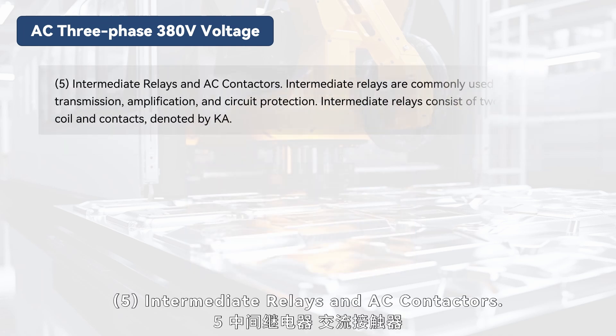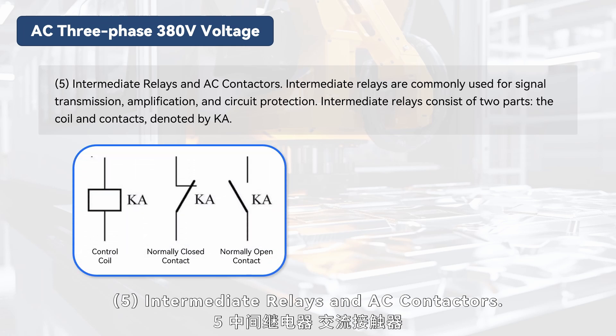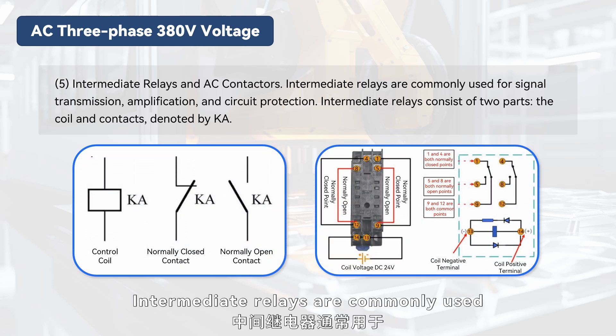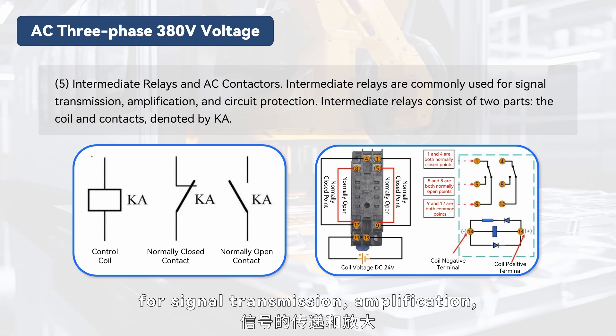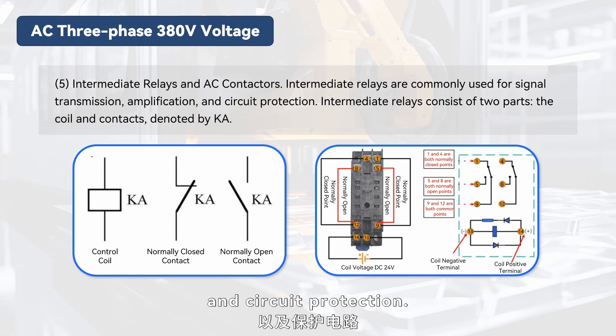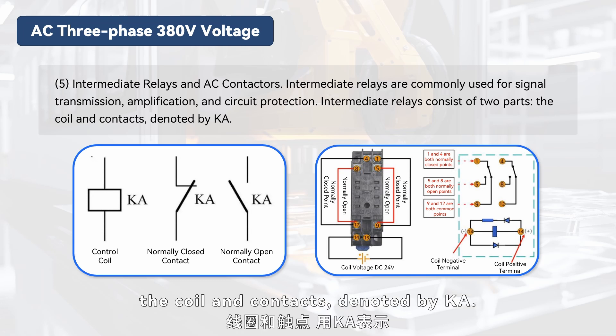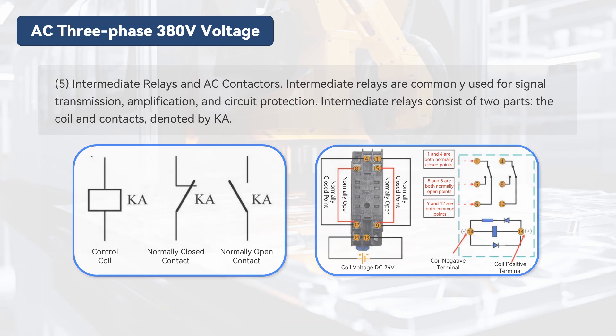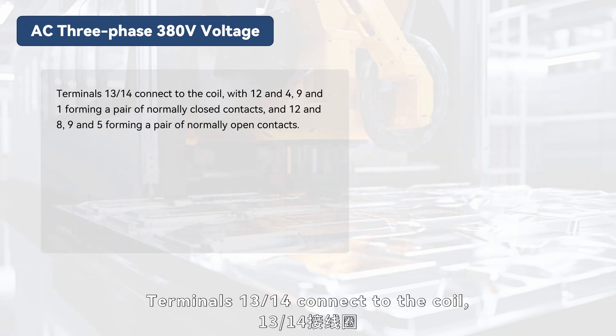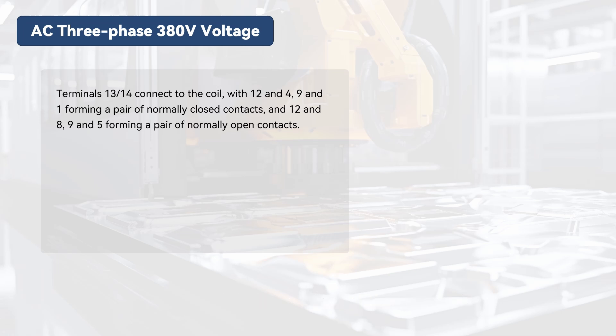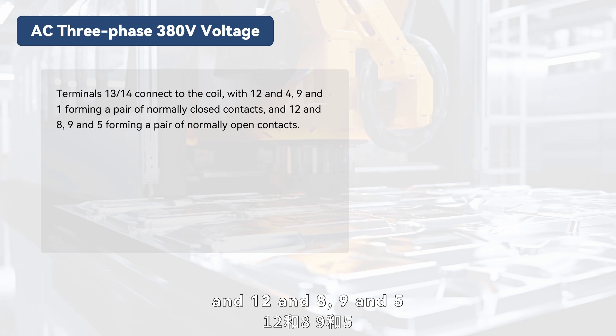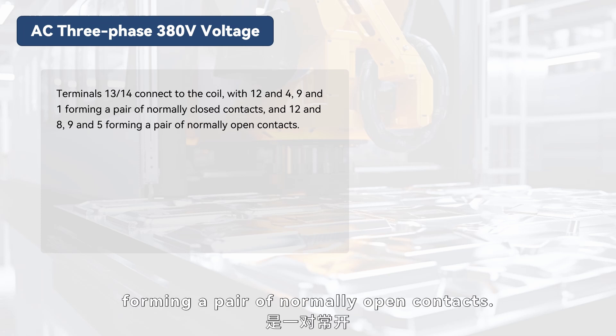Component 5: Intermediate Relays and AC Contactors. Intermediate relays are commonly used for signal transmission, amplification, and circuit protection. Intermediate relays consist of two parts: the coil and contacts, denoted by KA. Terminals 13 and 14 connect to the coil, with 12 and 4, 9 and 1 forming a pair of normally closed contacts, and 12 and 8, 9 and 5 forming a pair of normally open contacts.